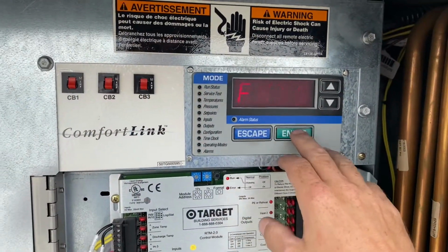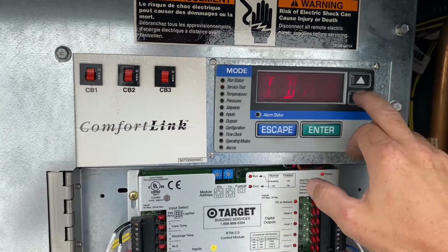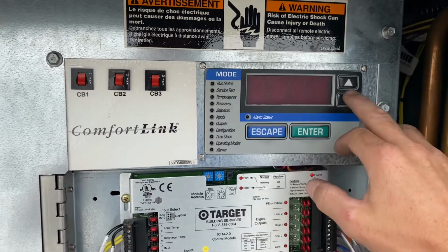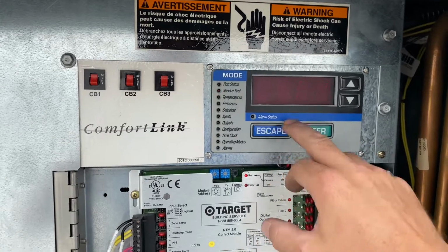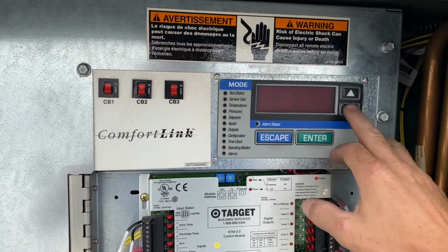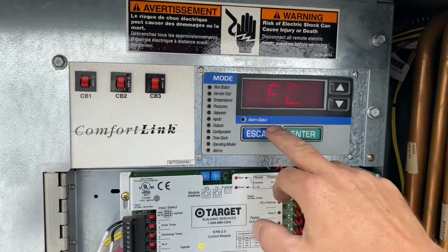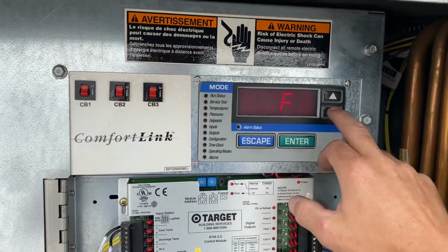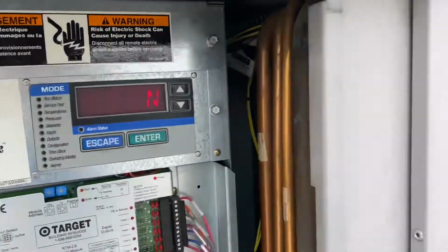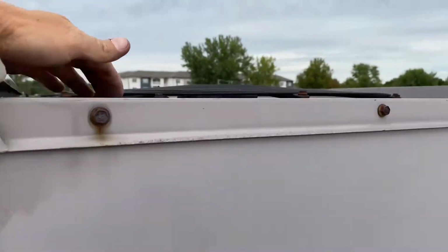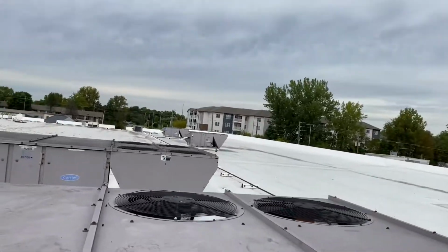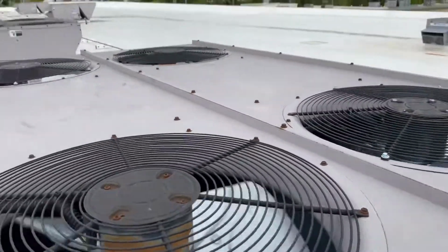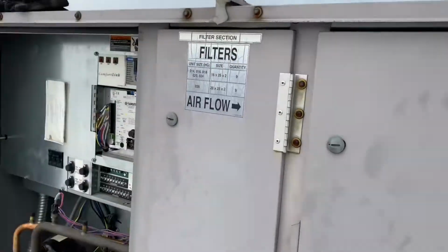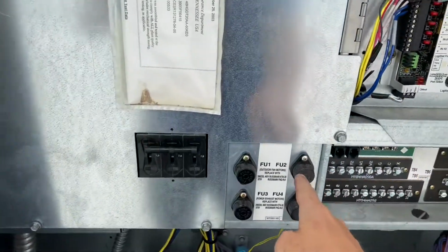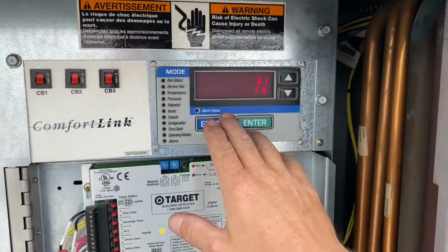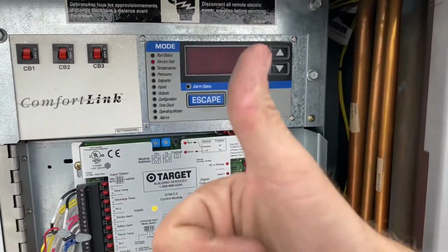2 new fans in, see what happens. Outdoor fan 1, on. Outdoor fan 2, on. Outdoor fan 3, on. All running good. Not popping that fuse either. I say we're good to go. Check.